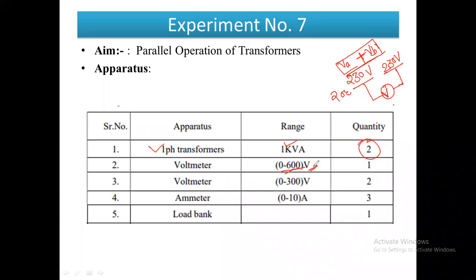Now another voltmeter is required, having a range of 0 to 300 volts, to measure the voltage of each individual transformer. Since there are two transformers, two such voltmeters are required.